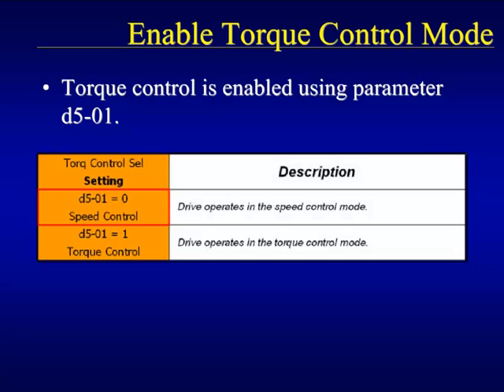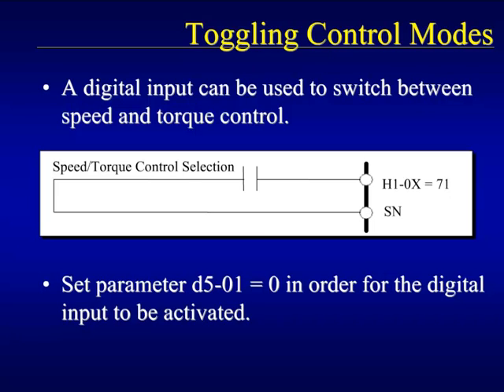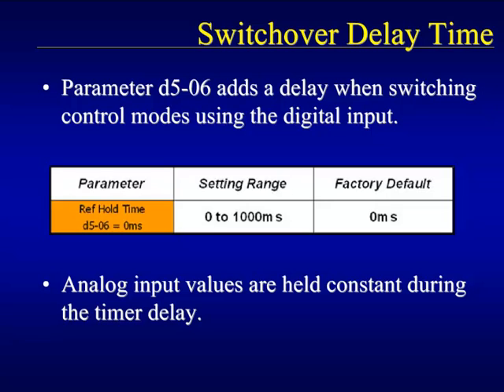Setting this parameter puts the drive in full-time Torque Control mode. If the drive will be switching between speed and Torque Control, a digital input can be set to act as a toggle switch between the two control modes. Setting any one of the multi-function inputs to setting 71 causes the input to take on this function. In order for the digital input to have any effect, parameter D501 must be set for speed control, setting zero. The user can then toggle between speed and Torque Control modes. When toggling between the control modes, a delay time of up to one second can be added to prevent instantaneous switching. Parameter D506 can be set anywhere between zero and one thousand milliseconds and is factory set for no delay.